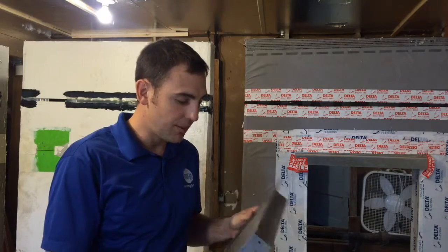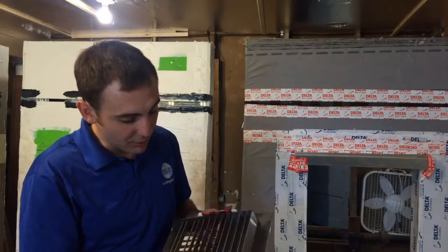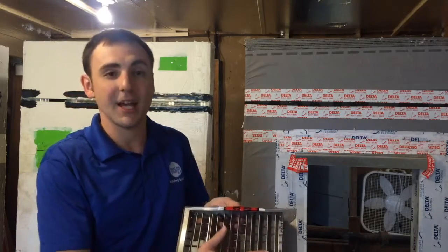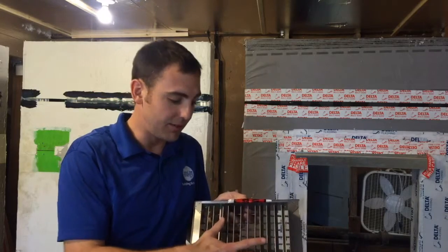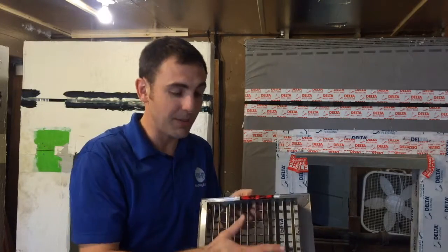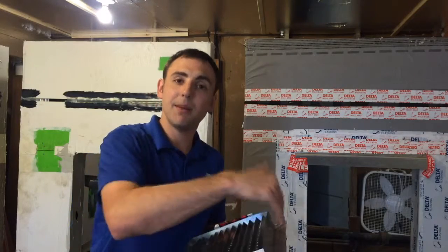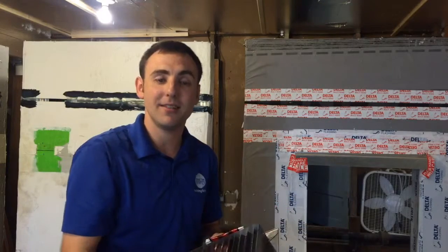So some of the cheaper grills and registers that you can buy actually block some of the air from coming out. You can see here that almost 50% of the surface area is blocked by the actual register itself. And the problem with this is you can then have pressure building up on the back side of this where the air isn't coming out. Almost as much as 10 CFM sometimes is stuck behind this register and not coming out the other side. When static pressure builds up like this, that connection where the supply boot meets the sheetrock is then under a lot of pressure, and the air can leak out around that seam if it's not sealed properly, once again affecting your airflow into your house.